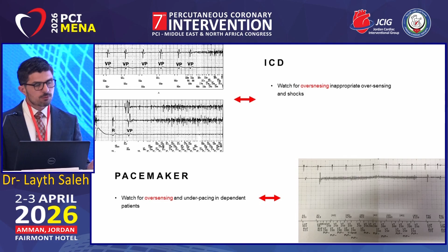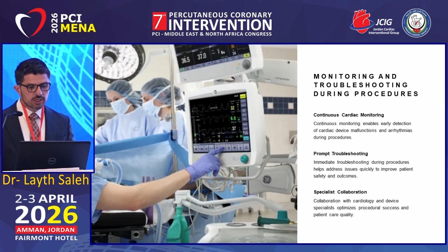Monitoring during the procedure is very important. Continuous monitoring with ECG, prompt troubleshooting. You have to always be able to recognize and address problems, which is either repeated shocks or underpacing because of the oversensing in the device. Specialist collaboration is also key, obviously. If there is any doubt about procedural management, then cardiologists or EPs should be consulted to discuss the proper management for sure.